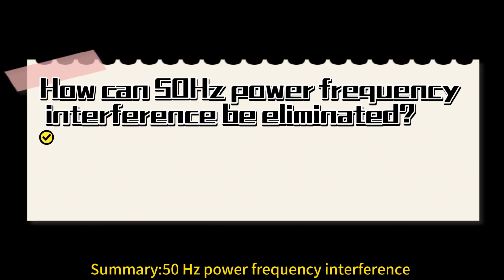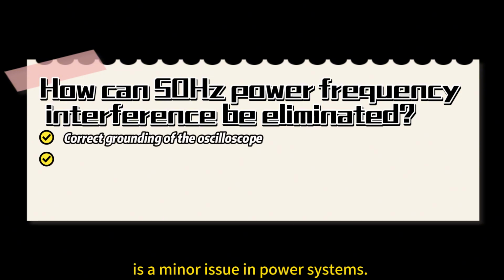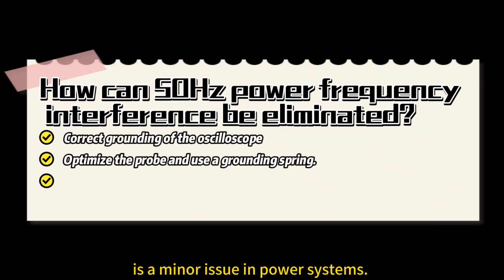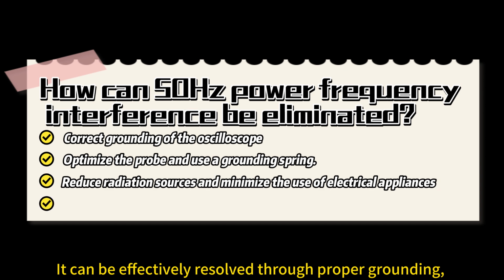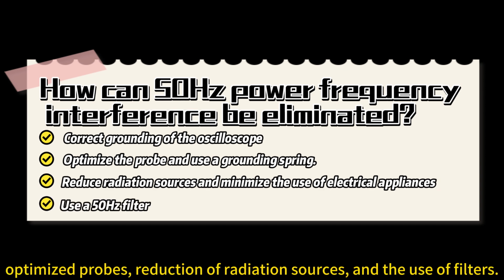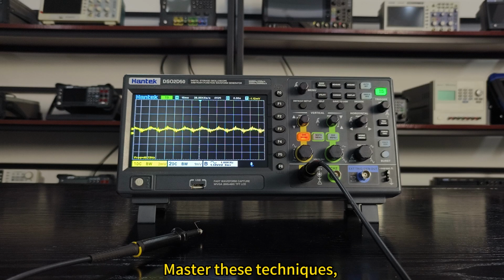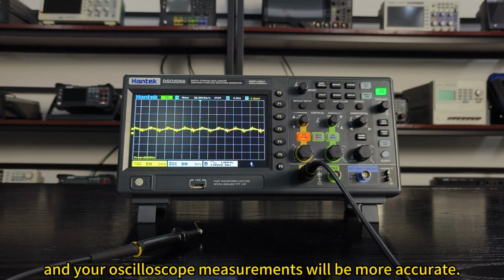Summary: 50 Hz power frequency interference is a minor issue in power systems. It can be effectively resolved through proper grounding, optimized probes, reduction of radiation sources, and the use of filters. Master these techniques, and your oscilloscope measurements will be more accurate.